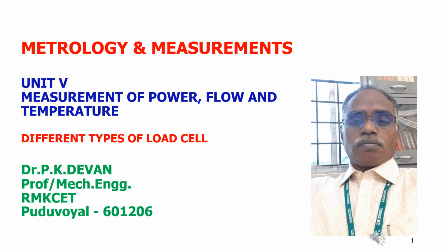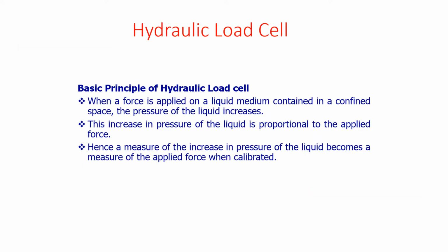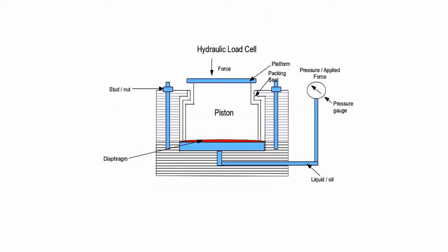Let us see the different types of load cells. First one is a hydraulic load cell. The hydraulic load cell works on the force balance principle. If you look at the diagram, we can understand that when the force is applied on the platform, the piston will exert a pressure or force on the diaphragm. The diaphragm is flexible, that is, it will deflect.